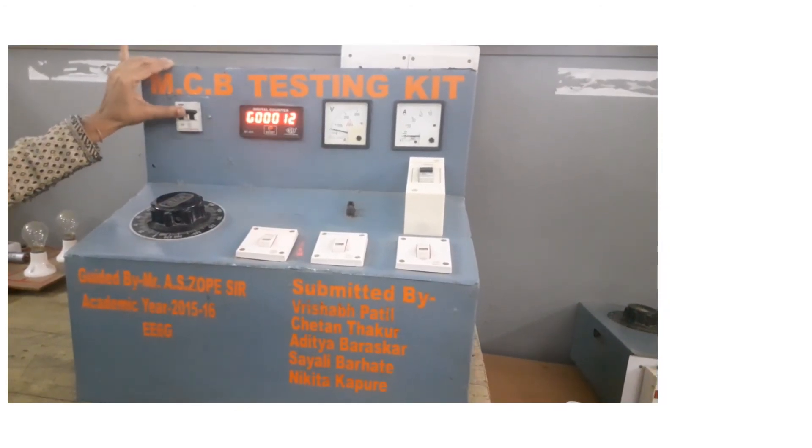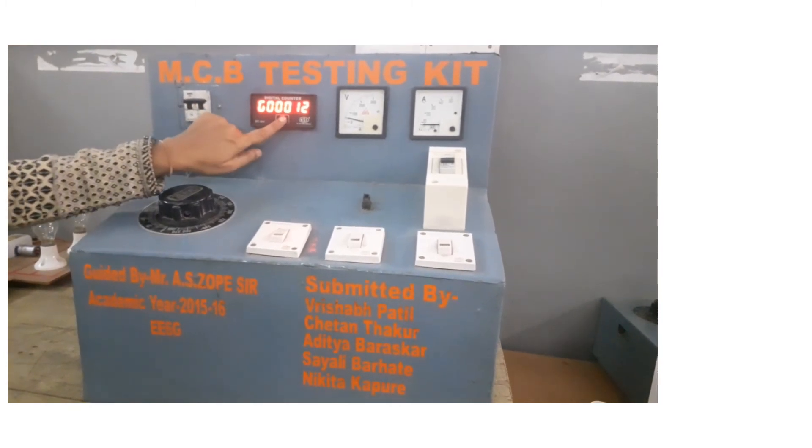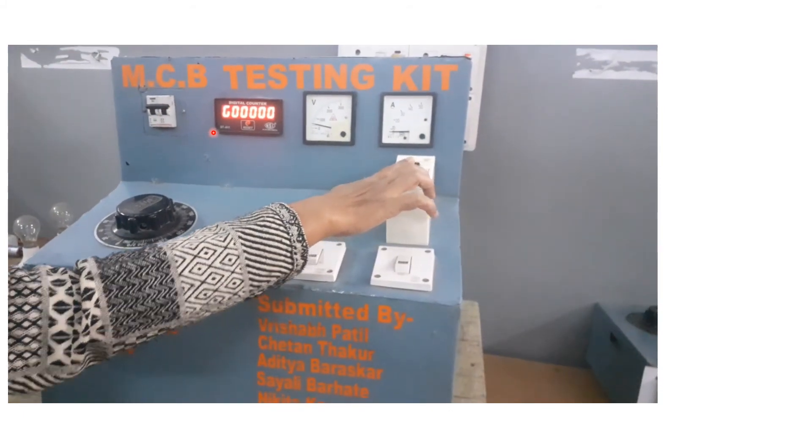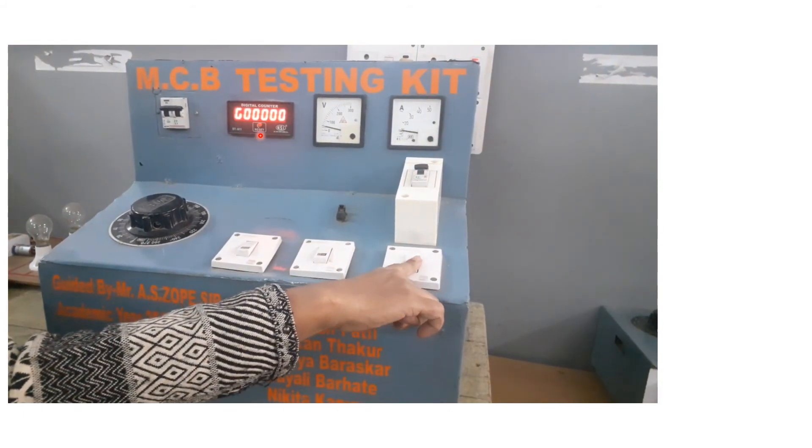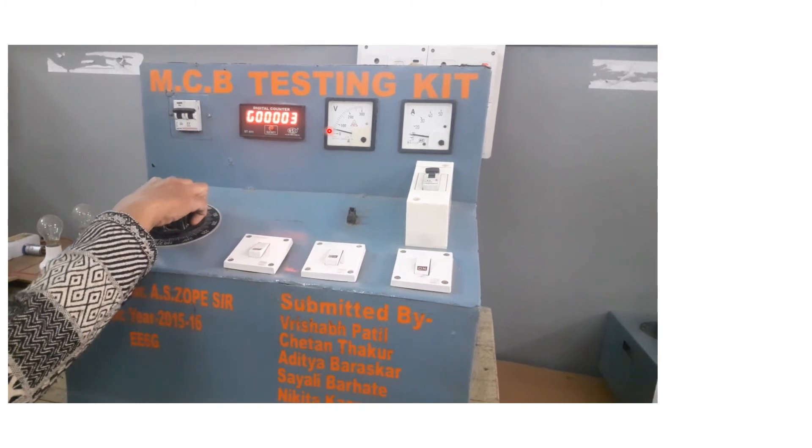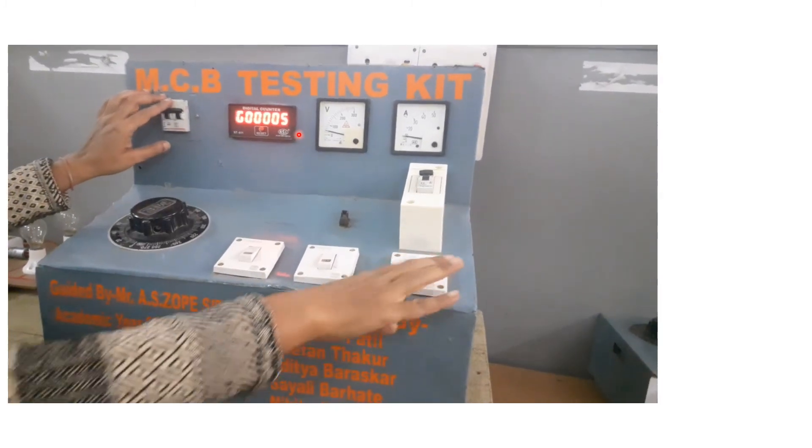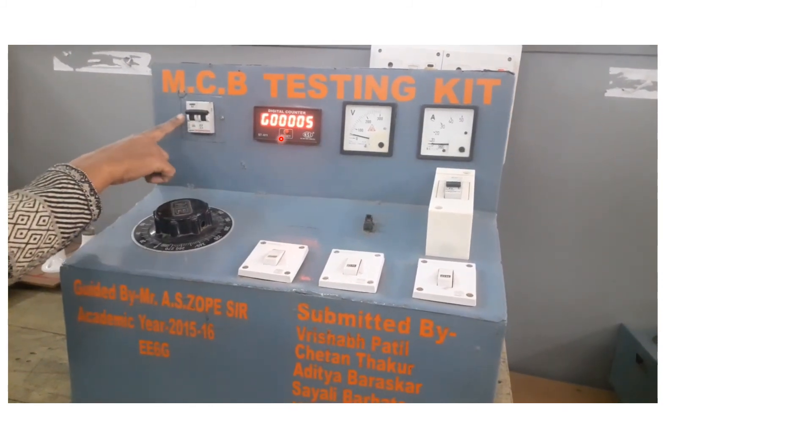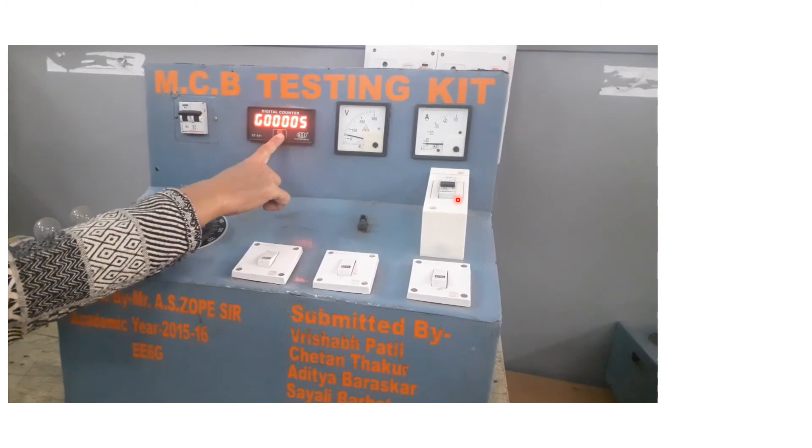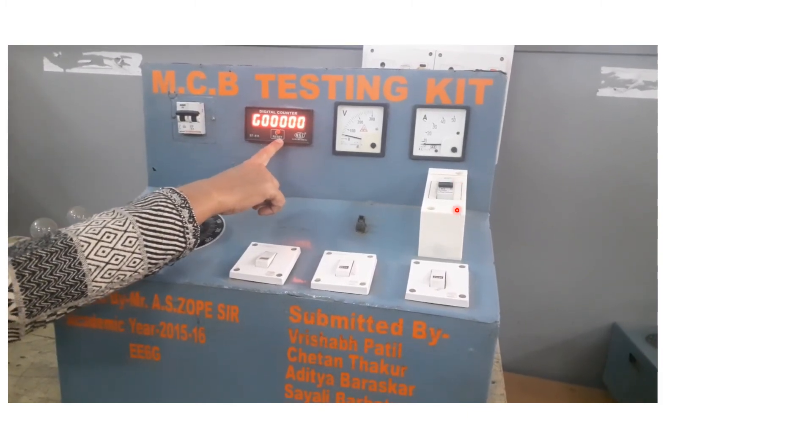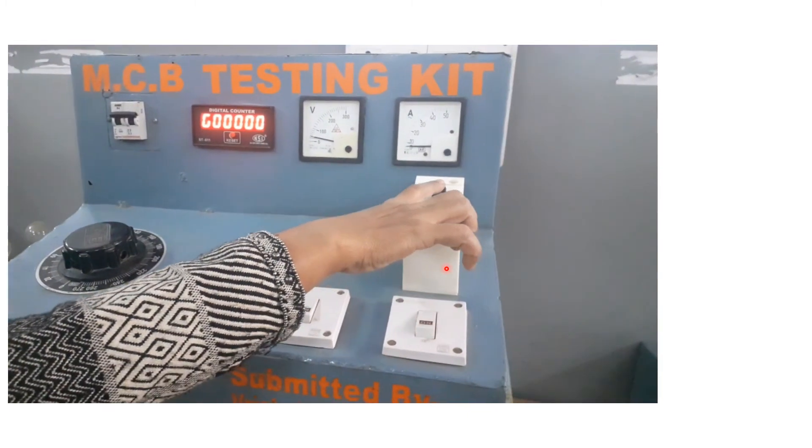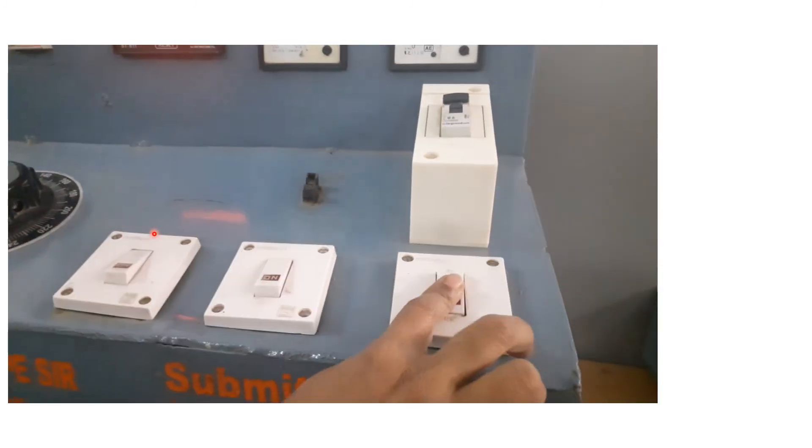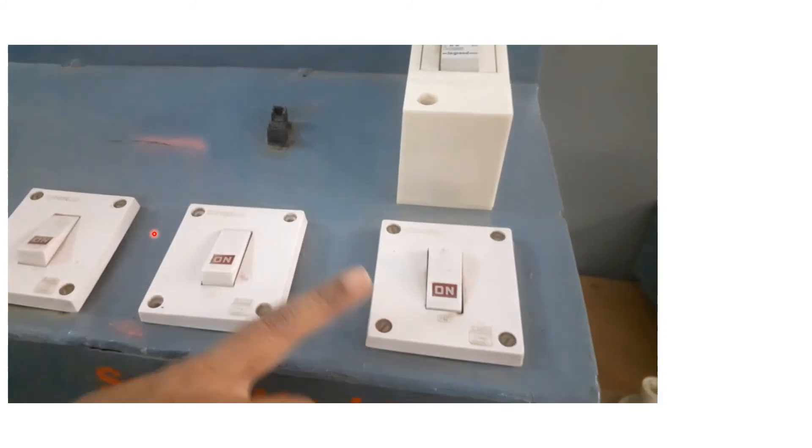Now we are performing the actual experiment on MCB testing. So to start it first you need to make the main MCB on. You need to check value of digital counter whether it shows you zero or not. If it shows some value then with the help of this knob you have to make it zero. You have to reset it. You are having this MCB under test. Make it on. Make the main switch S3 on and then with the help of this variac you need to apply the value of rated value of current. So rated value is 6 ampere. So now here I am going to apply 10 ampere and we will see how much time your MCB trips.